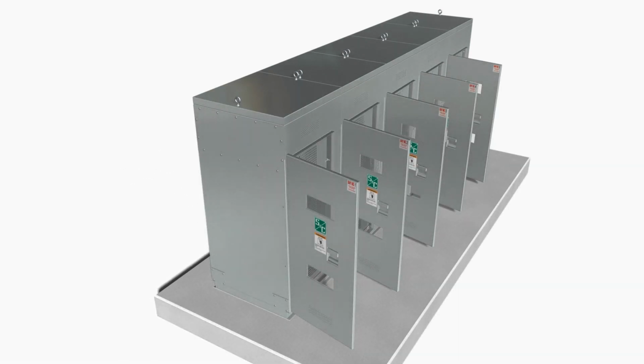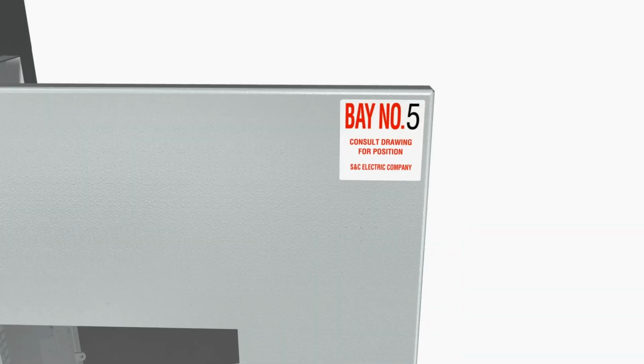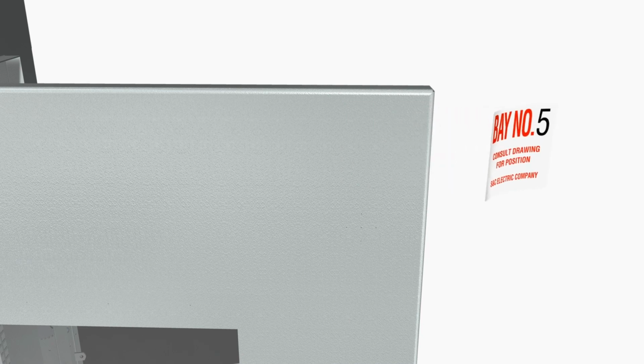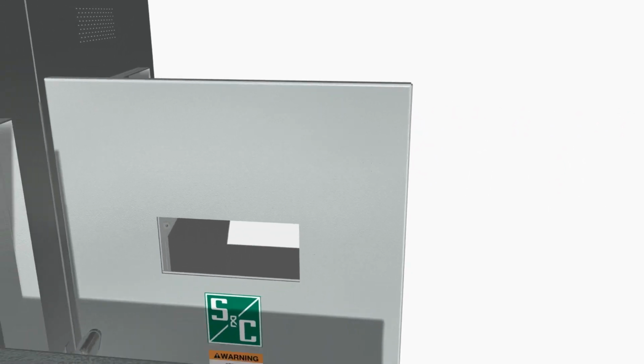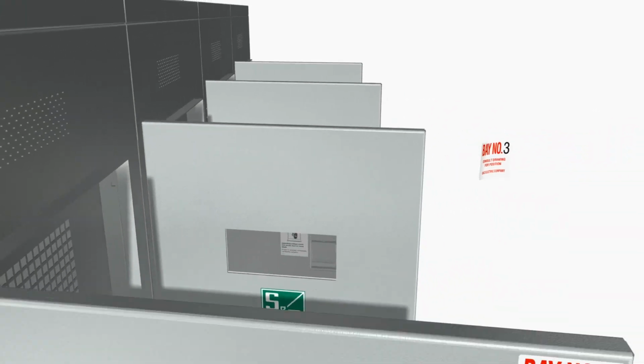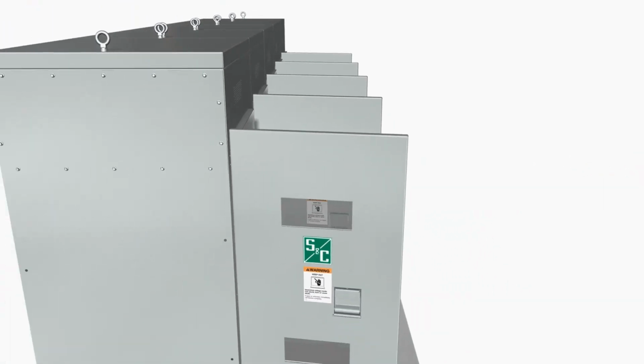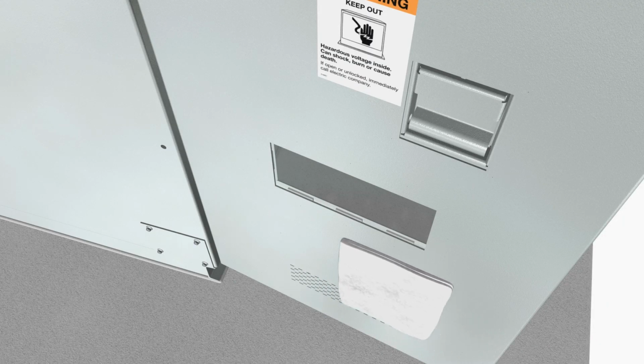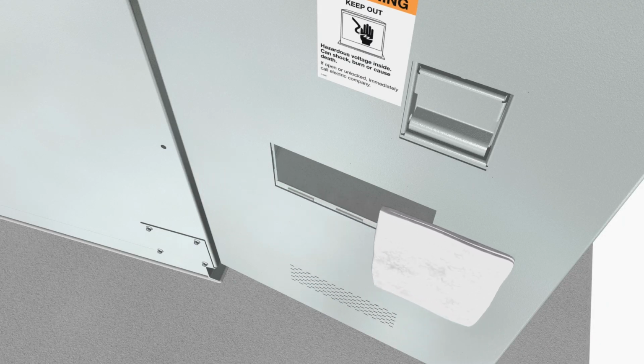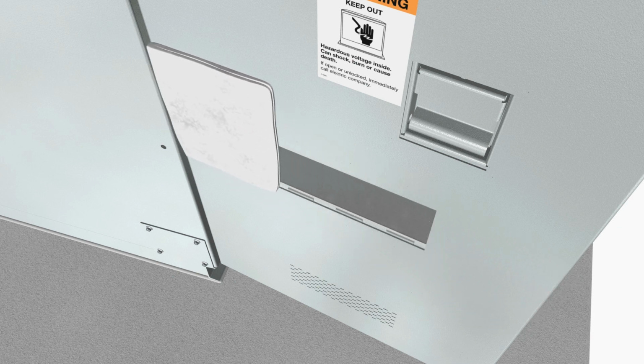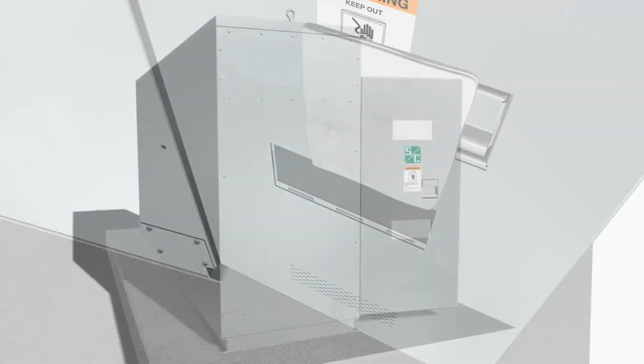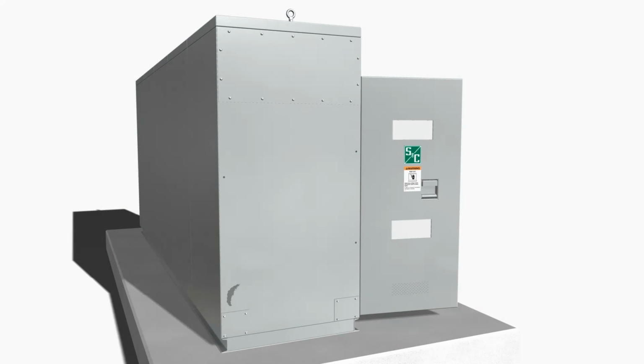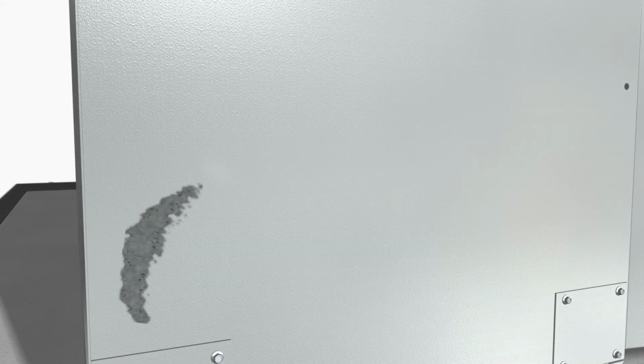Step 24. Remove all shipping tape, bay number labels, and any polyethylene or tape from vents. Remove any remaining adhesive. Wipe down the exterior of the switchgear with a clean, damp cloth and, when thoroughly dry, touch up any scratches and abrasions using the touch-up primer and paint provided, observing the application instructions included on the aerosol cans.